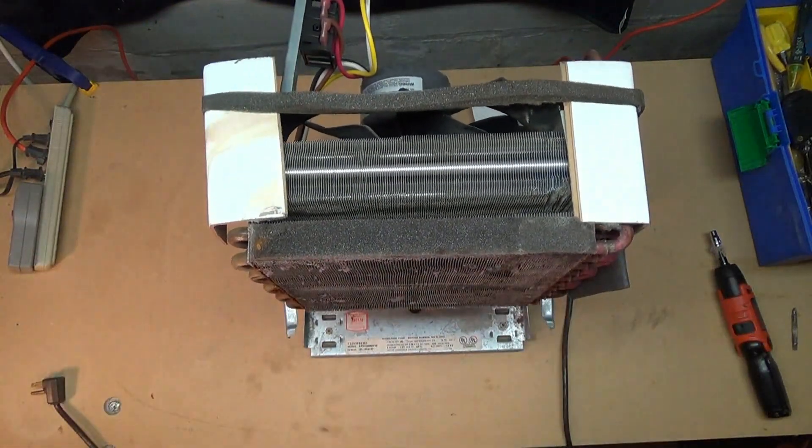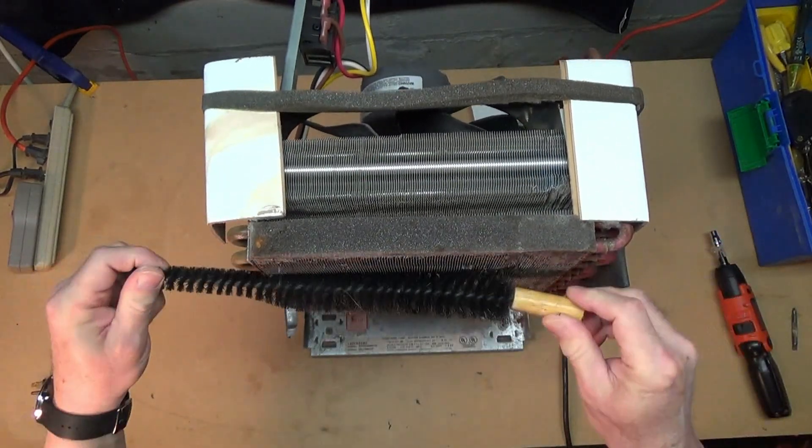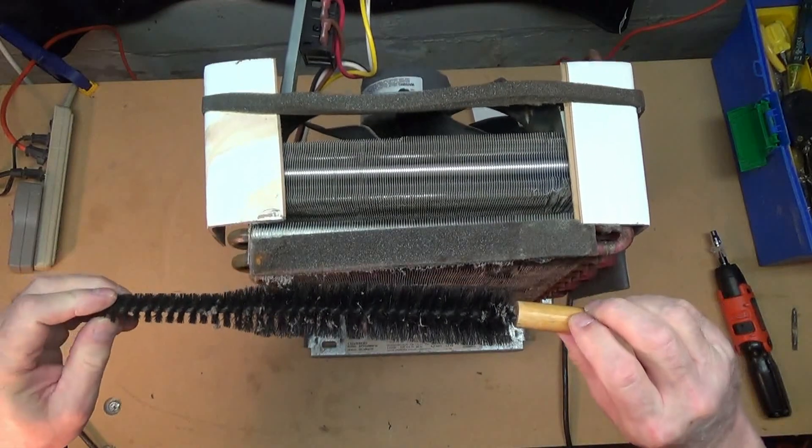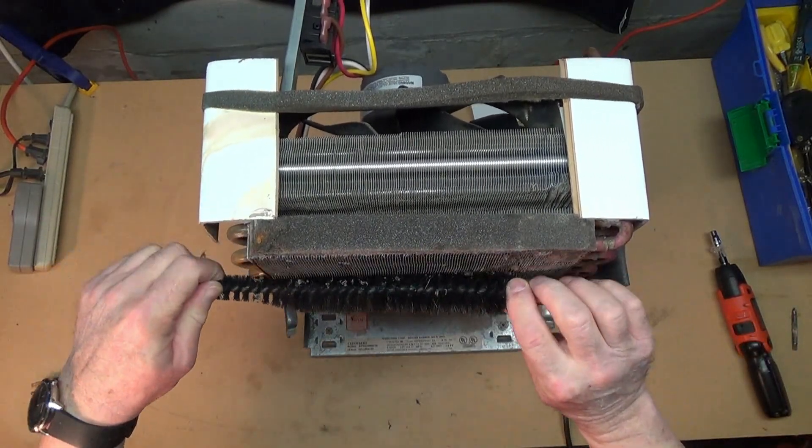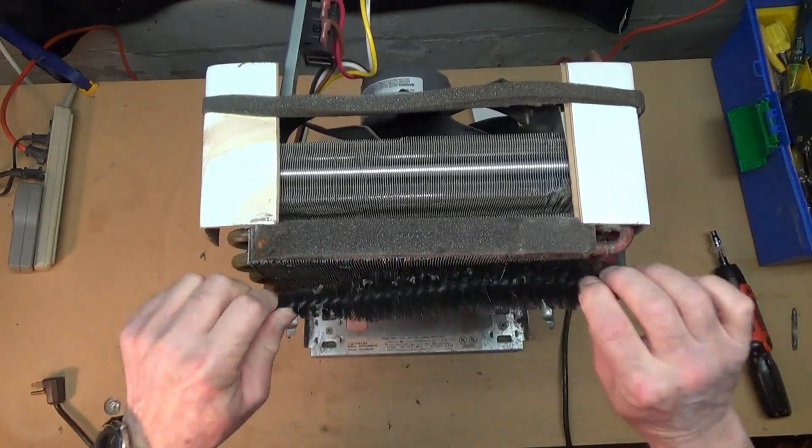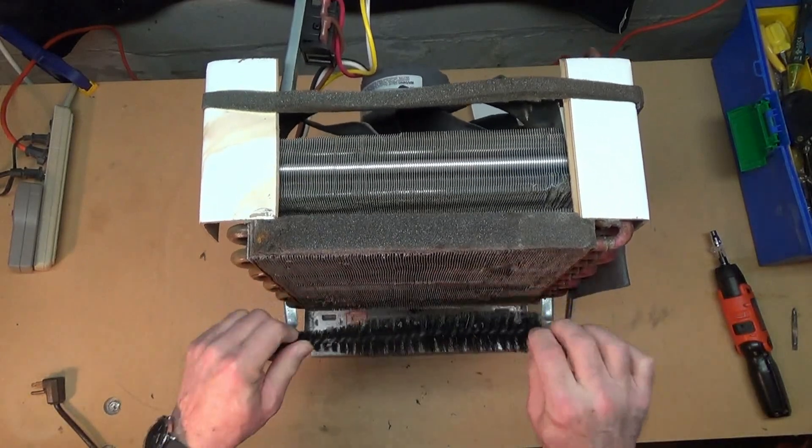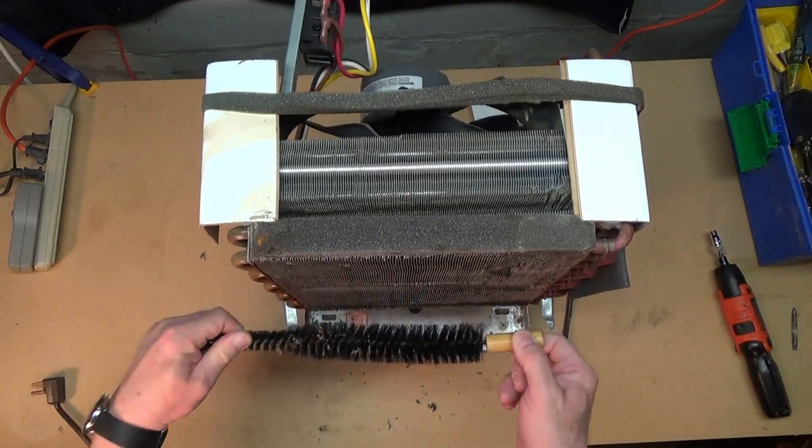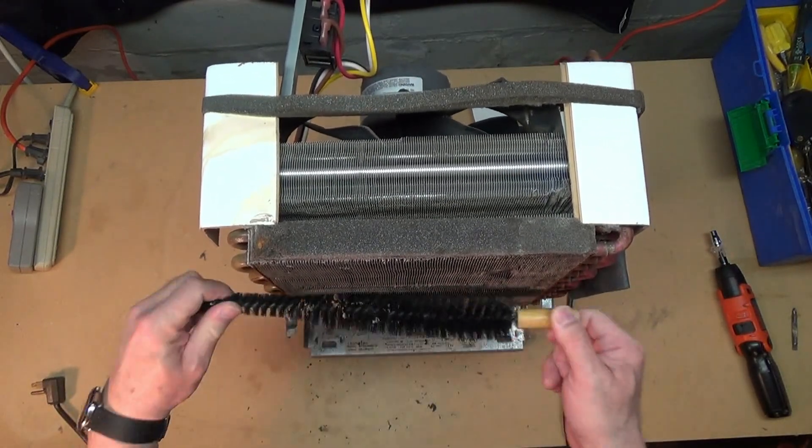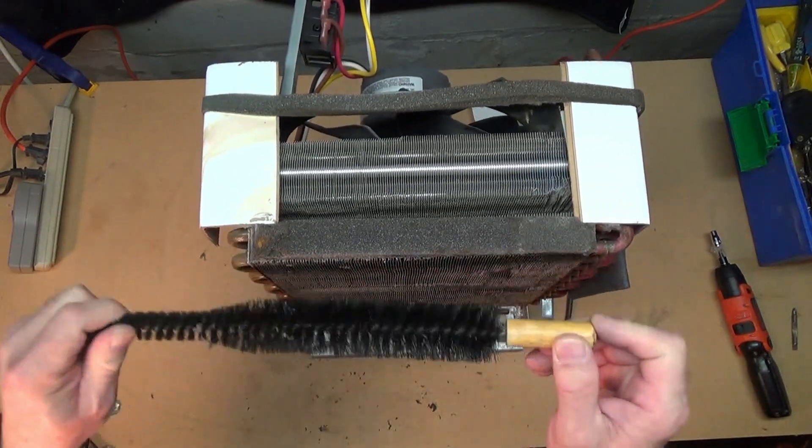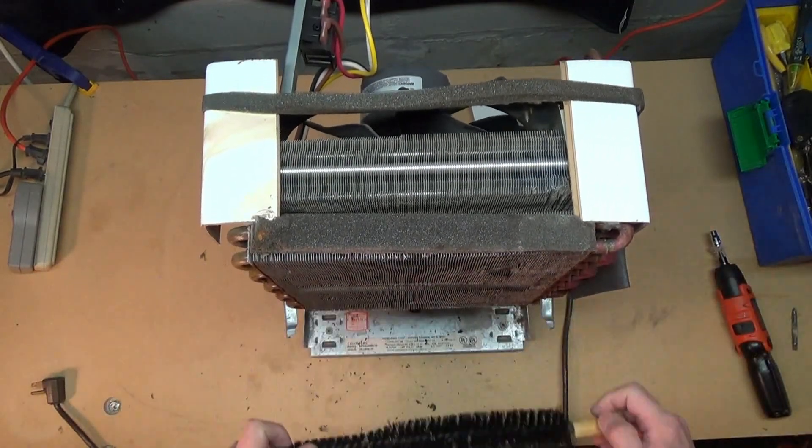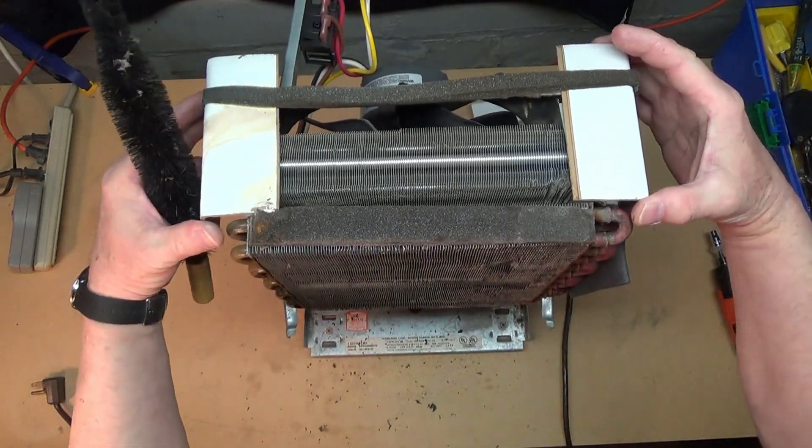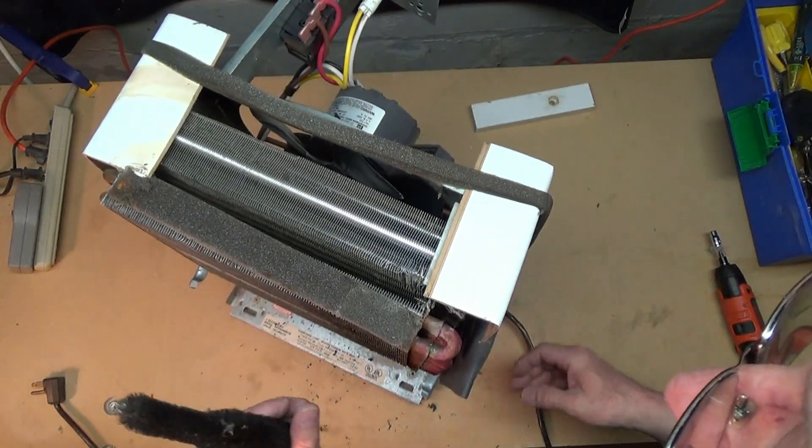If I were to bet about a place where these would start to freeze up, that might be one of the places. What I'm going to do is I'm going to take this brush—it's just a radiator brush—and I'm going to run it in the same direction as the coils and get as much of the dust out of there as I can, and then I'm going to straighten the coils out where they're smooshed, at least as best I can, so that air will flow through them again.